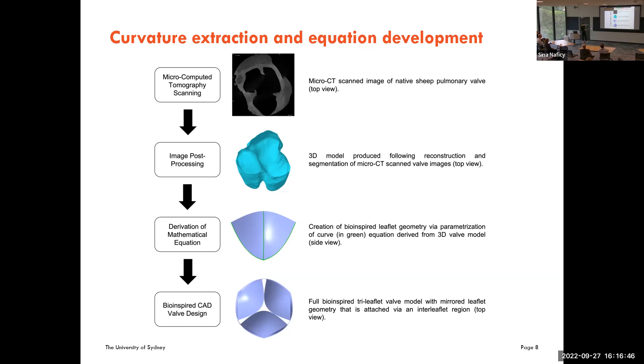From this single leaflet we extract the curvature using curvature extraction tools on CAD software. The most important part is the middle curve extracted from the 3D model, defined using a mathematical equation. That equation is plotted parametrically on CAD software to develop the leaflet shape, which is then mirrored across the central axis to produce a tri-leaflet valve.